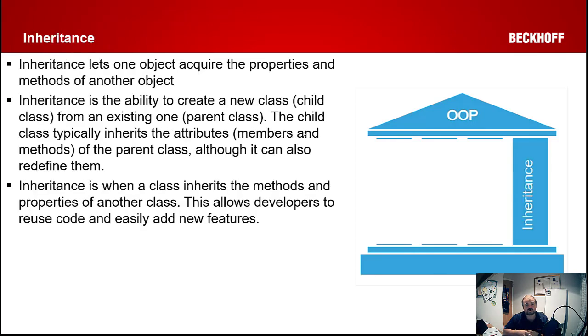Inheritance is a very powerful tool and what it basically allows you to do is pass the properties and abilities of one class to another. So for example, taking our axis class, we could have that and inherit another axis class that adds some extra functionality, but it gains all the base functionality from what we refer to as the parent, the original one. What that allows you to do is maintain really nice close-coupled hierarchies of implementation. Let's say your axis class just does an absolute move, but you wanted to be able to do a velocity move. You inherit from that so you still have the ability to do the absolute move, all the things to enable, disable, reset that you've implemented in the one that can do the absolute positional move are still there for your velocity, and then you can add to it using inheritance. That's a way of not repeating code, because you could obviously just make another function block and copy-paste all the code in, and that would be a waste of your time.